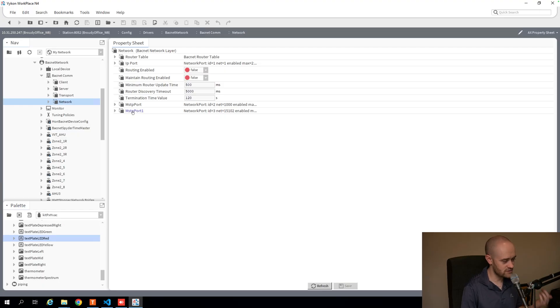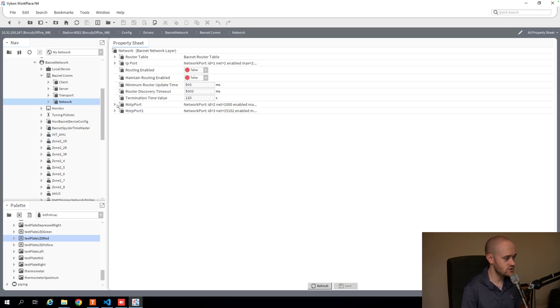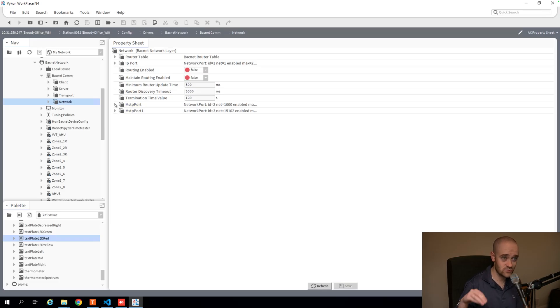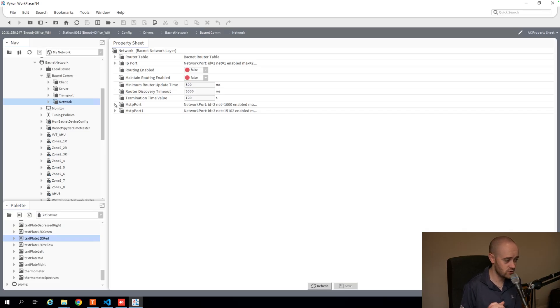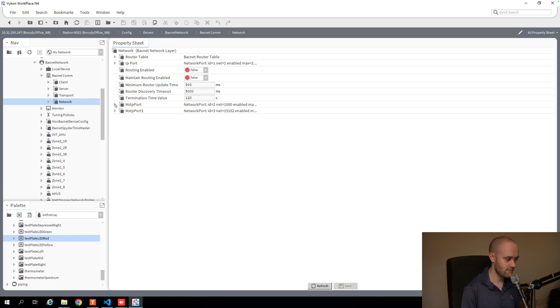I've got wired RS-485 devices being brought into the Jace, and because of that, I've got two ports here making that interface between the physical hardware on the Jace that's talking to the 485 trunk and the software that's actually running BACnet and making everything talk.